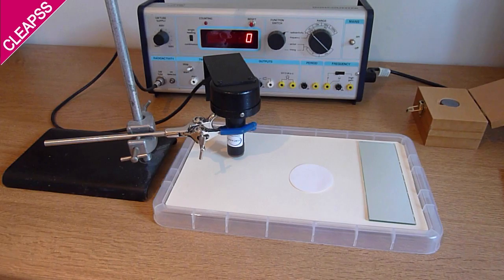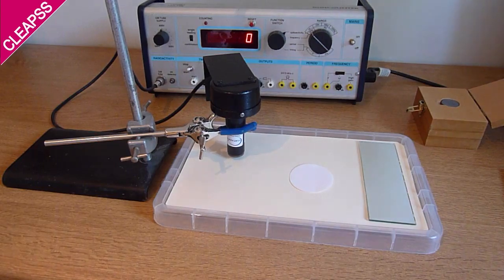You need to do a background count for 1000 seconds. If you have already done this in the past hour when carrying out the relative GM tube efficiency, you do not need to do it again. Divide the count you got over 1000 seconds by 10 to get the average count over 100 seconds.